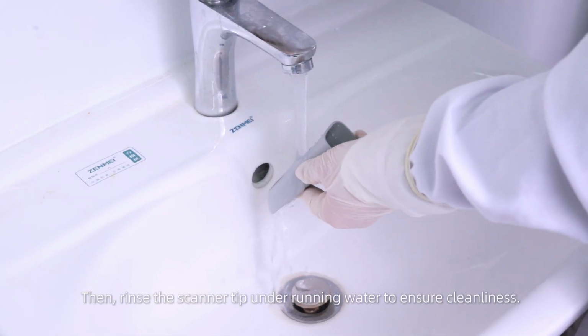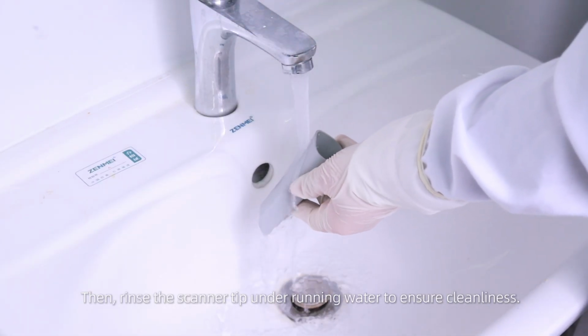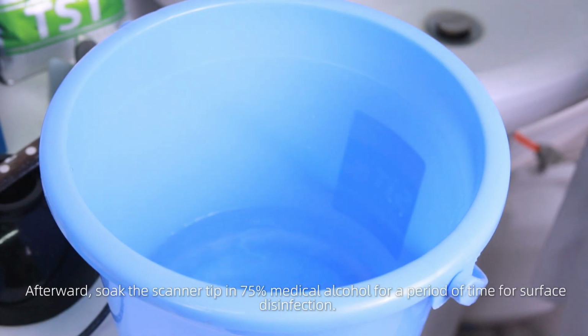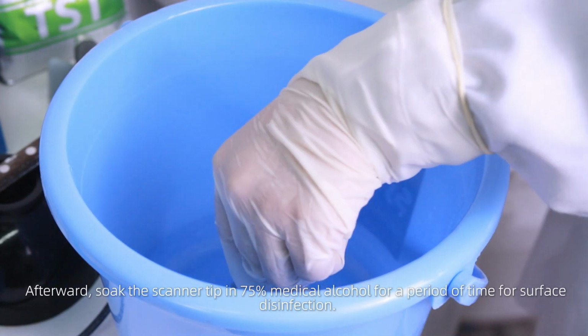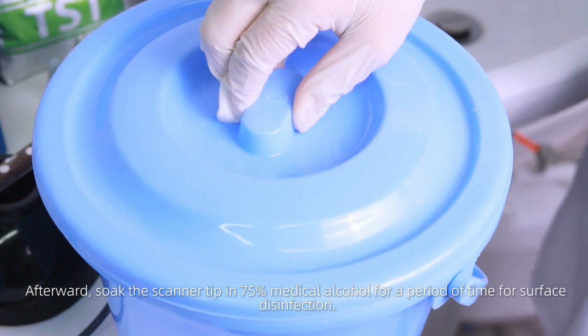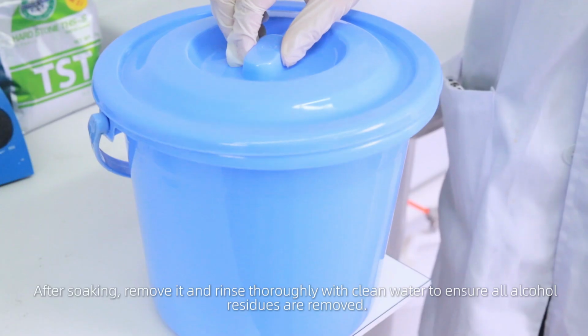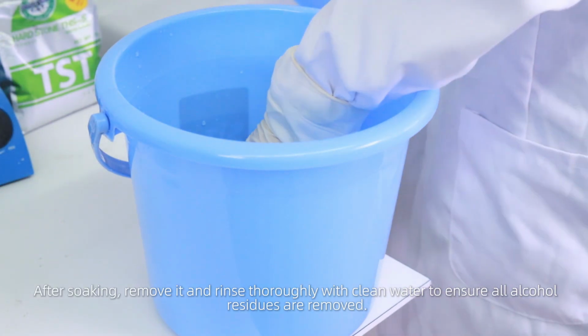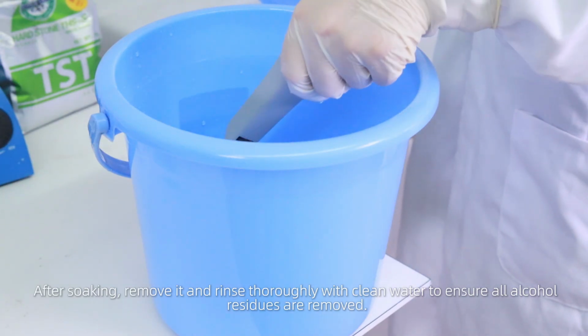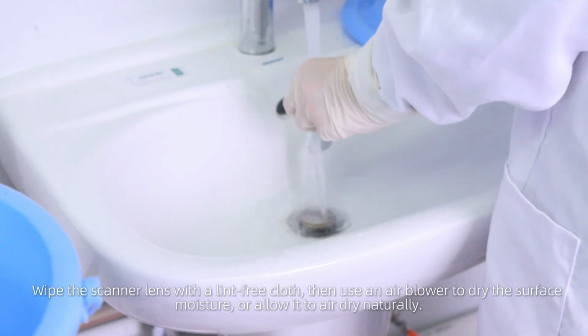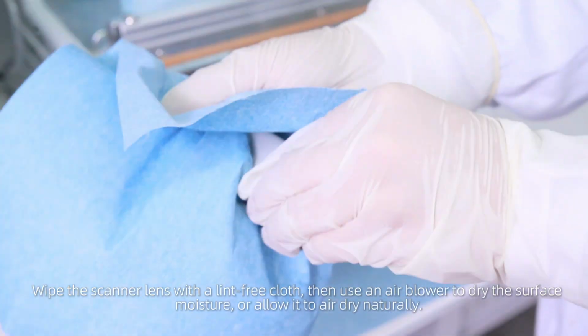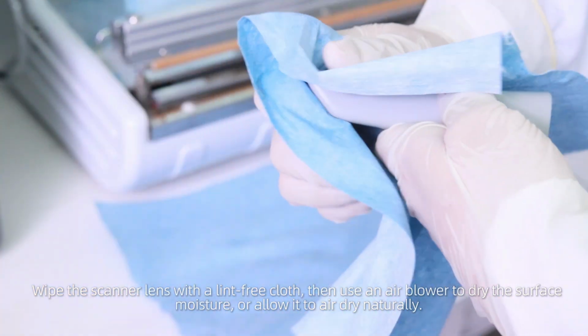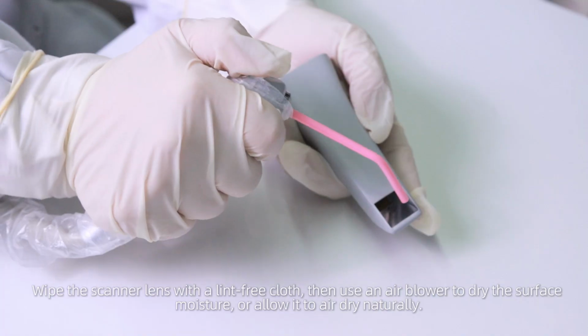Then, rinse the scanner tip under running water to ensure cleanliness. Afterward, soak the scanner tip in 75% medical alcohol for a period of time for surface disinfection. After soaking, remove it and rinse thoroughly with clean water to ensure all alcohol residues are removed. Wipe the scanner lens with a lint-free cloth. Then use an air blower to dry the surface moisture, or allow it to air dry naturally.